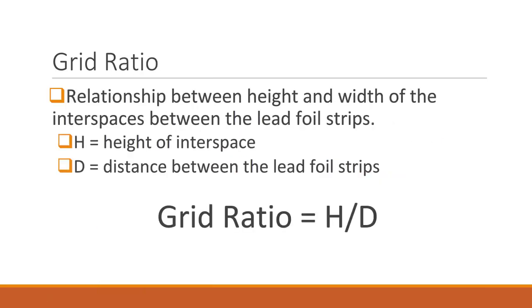Grid ratio is the best way to determine a grid's efficiency. The relationship between height and width of the inner spaces between the lead foil strips determines how much scatter radiation is able to pass through the grid. You need to memorize that grid ratio equals H over D, where H is the height of the inner space and D is the width of the inner space, also stated as the distance between the lead strips.